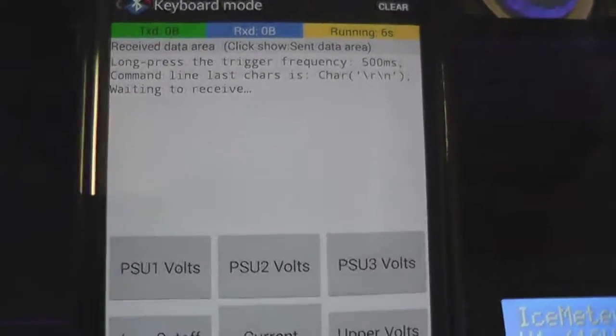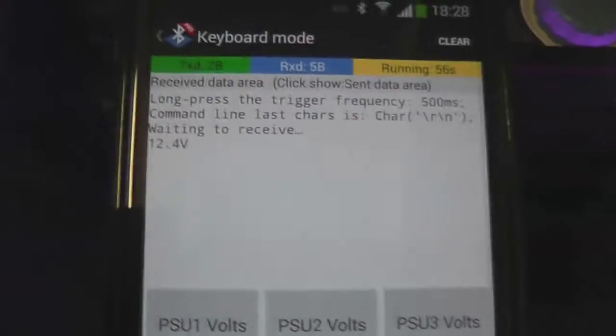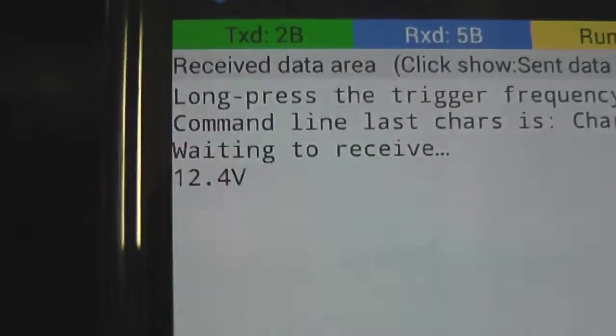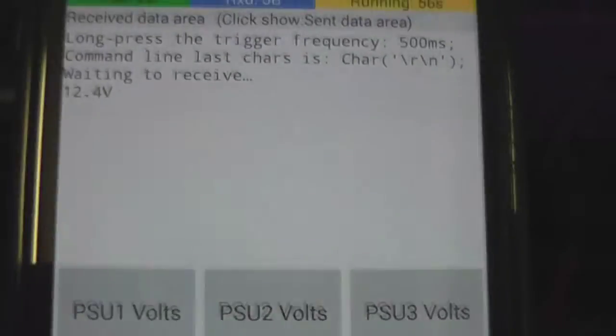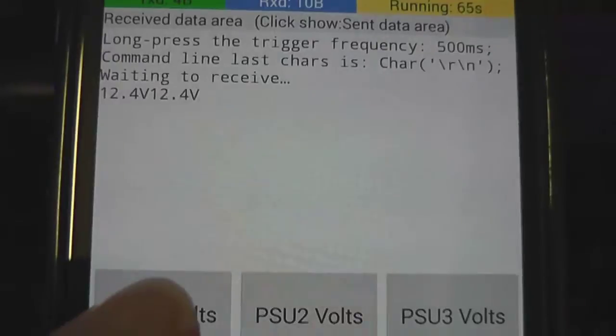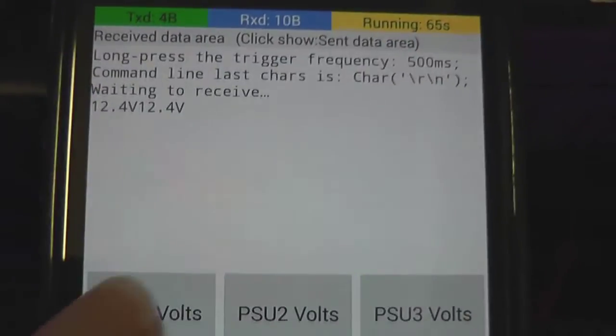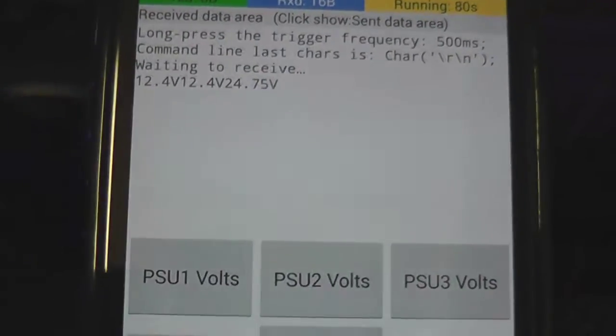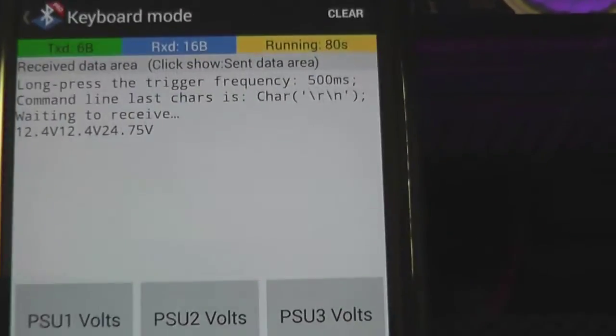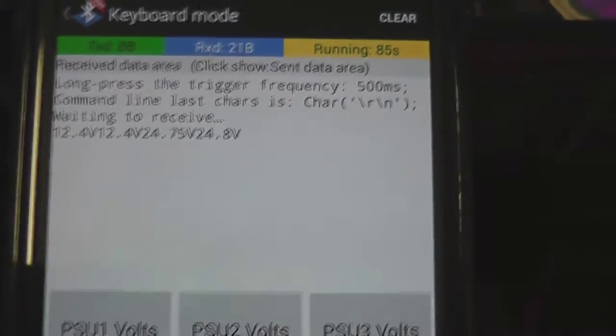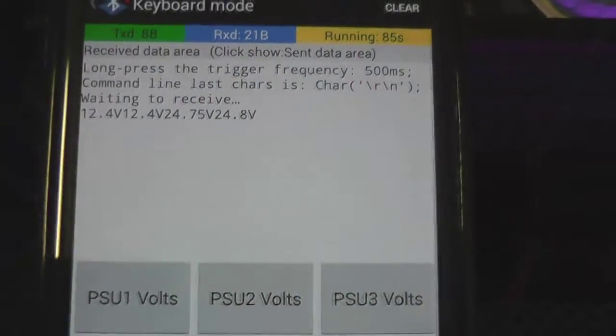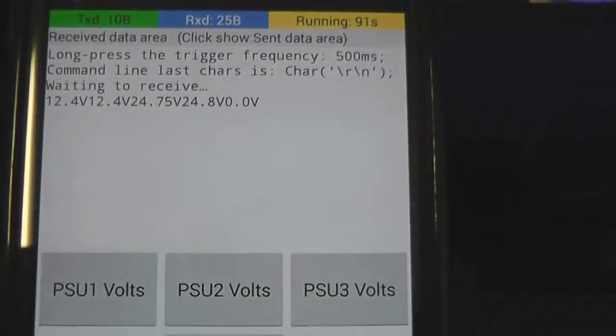So if I come across to this, show you the screen, and press PSU 1, as you can see we're showing 12.4 volts. I can press it again while we're there and we're getting live information of 12.4. Scroll to V2, which is the two combined, 24 volts, 24.75, 24.8 according to that. Press the PSU 2 volts button and we've got 24.75. That's the voltage coming out of it at that present time. 24.8, there you go. If I press PSU 3, there is no PSU 3, so it's going to return 0 volts.